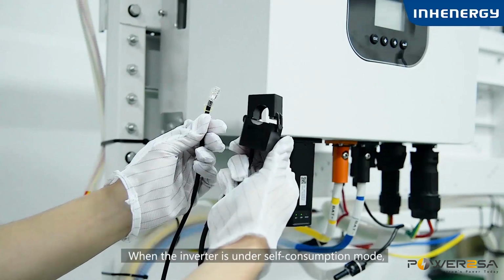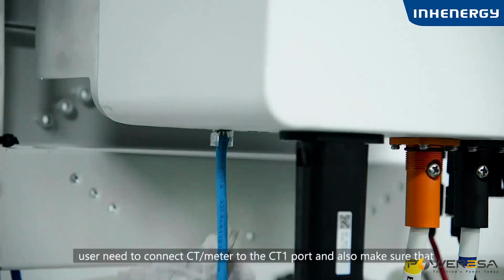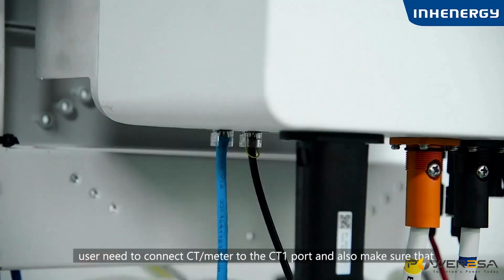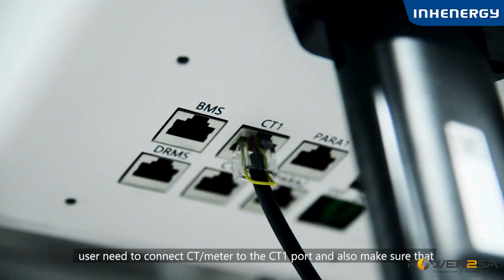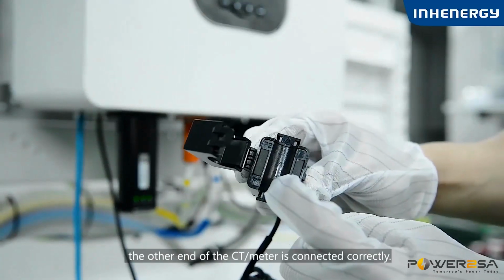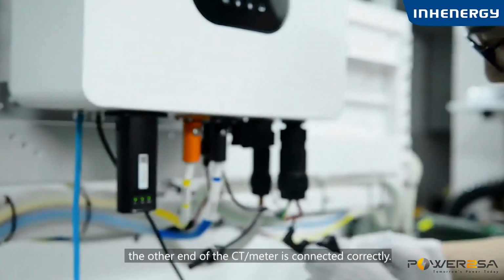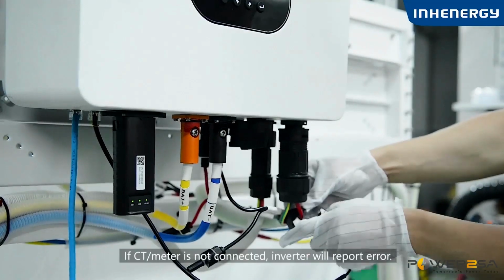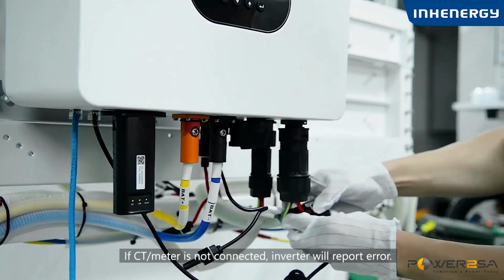When the inverter is under self-consumption mode, user needs to connect the CT or meter to the CT1 port and also make sure that the other end of the CT or meter is connected correctly. If CT or meter is not connected, inverter will report error.